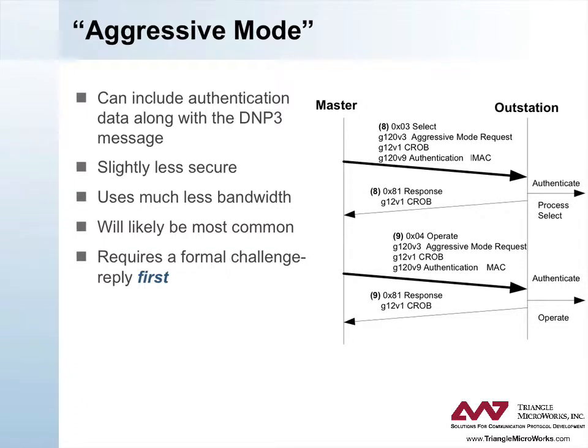Because the complete challenge-reply sequence adds several messages to a DNP3 transaction, the secure authentication specification permits devices to use an aggressive mode, in which the sender assumes the message will be challenged and transmits a MAC in the same message being authenticated. Here is an example of a select-operate sequence using aggressive mode. The master sends a message with a select function code and a CROB object as before, but precedes the CROB with an aggressive mode request object and follows it with a MAC object.